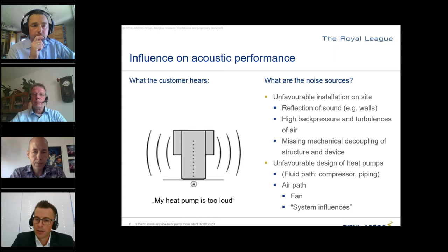Further, if you have high back pressure levels or turbulence of air, this will create sound at your heat pump. Or what is possibly even worse is a missing mechanical decoupling of the structure where you install the heat pump and the device itself. Coming a bit to the manufacturer's part of fans, there can be an unfavorable design of heat pumps, especially regarding the air path.